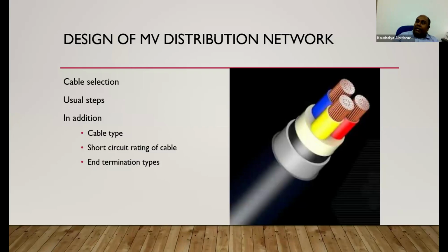Because of the lower current level, lower steady state current, any cable usually goes okay with your installation cable design. Cables manufacturing start from maybe 70 millimeter squared, and which can accommodate somewhere like 200 odd amperage. At 33 kV, a 2 MVA transformer is using somewhere around 35 amperes, and a cable having a 70 millimeter cross section is more than enough.